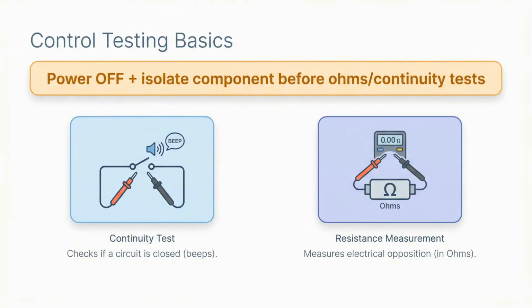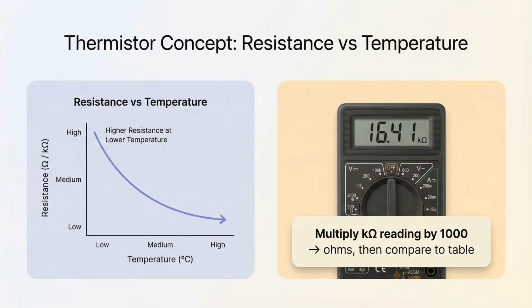For controls, the key foundational tests are continuity and resistance. Continuity proves there's a complete electrical path, often just whether switch contacts are open or closed. Resistance is measured in ohms. The critical rule is power must be off, and the component should be isolated from the circuit before doing continuity or resistance testing. Electronic controls often use thermistors. The controller interprets resistance as temperature. Here, higher resistance means lower temperature, and as resistance drops, temperature rises. When a controller can't read a sensor, the troubleshooting path is to test the controller terminals, the wiring run, and the thermistor itself, isolating and testing each part separately.